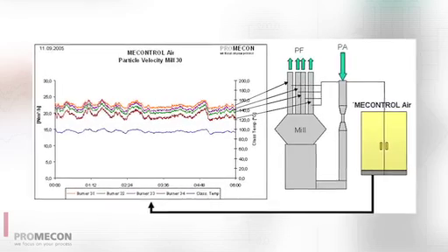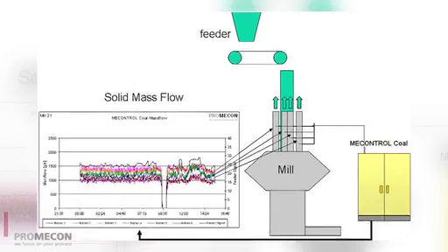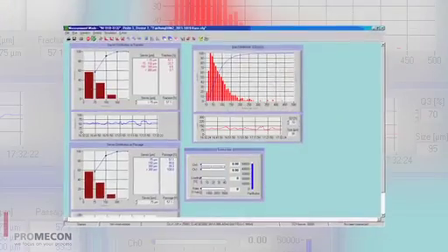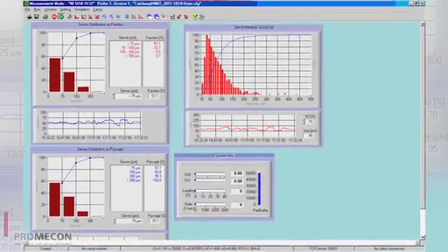The question now is: what are the parameters that we should measure in order to wrap all this up? The first parameter is what is the air going not only into the mill, but also out of the mill — so the air balance through the mill. Secondly, you need to know the solid mass flow balance through the mill, including the coal mass flow in and out, and velocities. Thirdly, you need a fast temperature measurement on the classifier to control the drying process to a very constant operation. And last but not least, you want to know the final product fineness — so online measurement of coal fineness. These four issues are what we want to measure online in order to optimize the performance of the pulverizer.